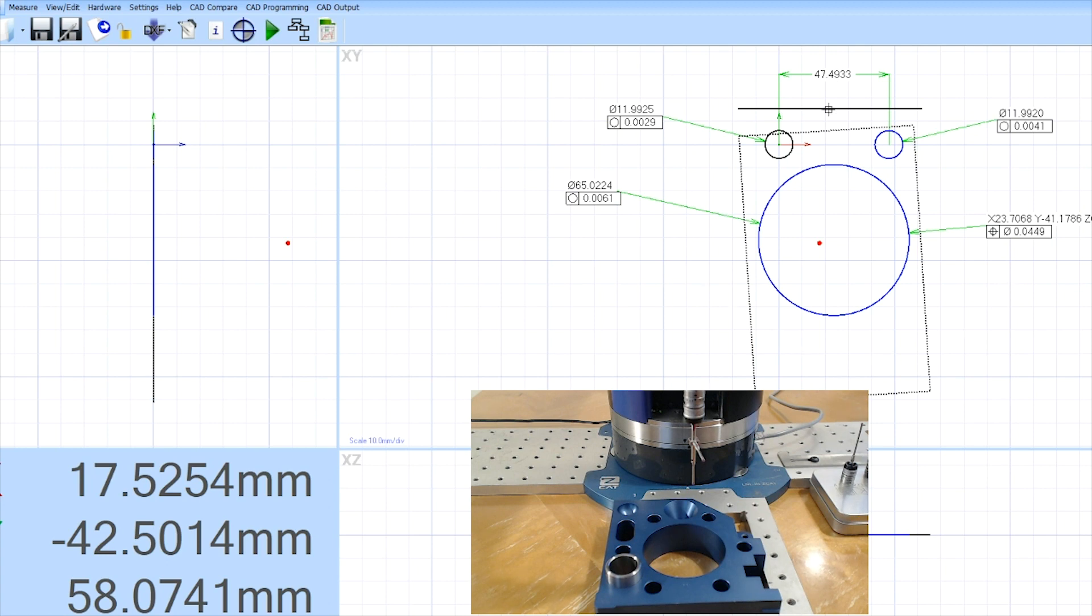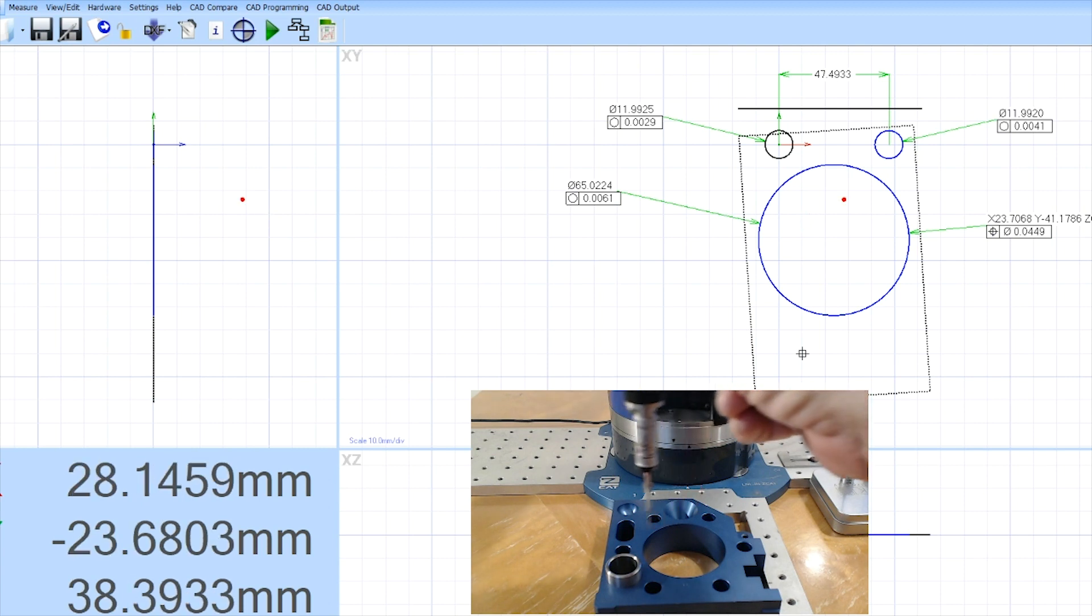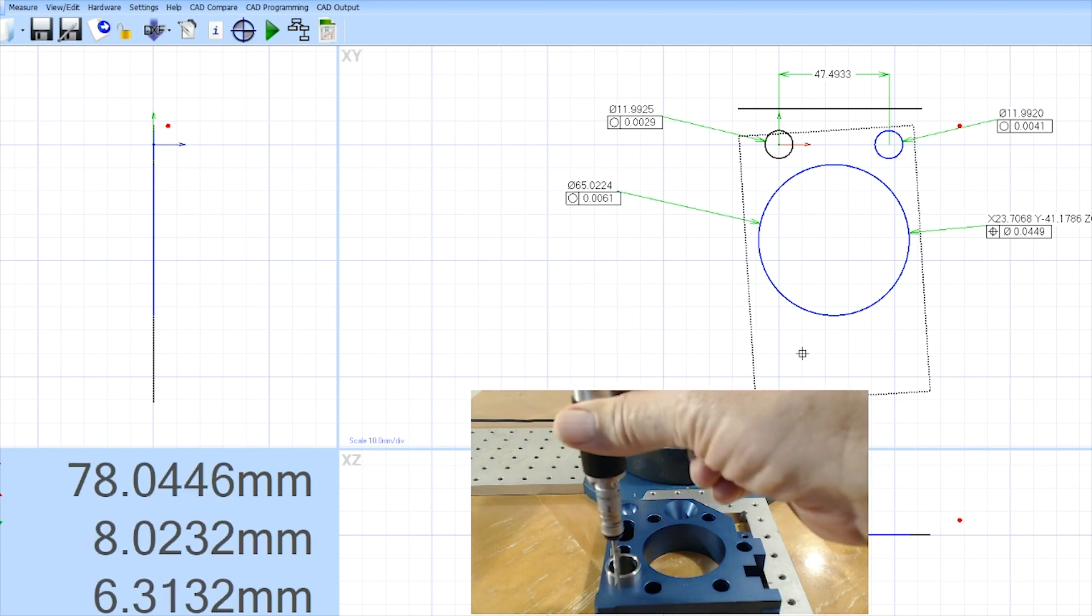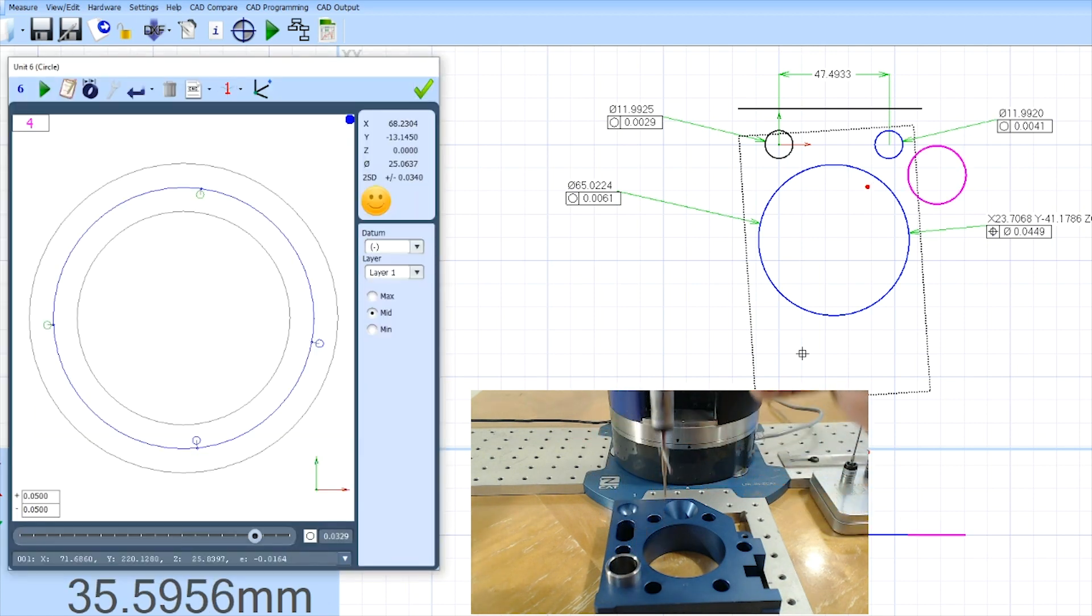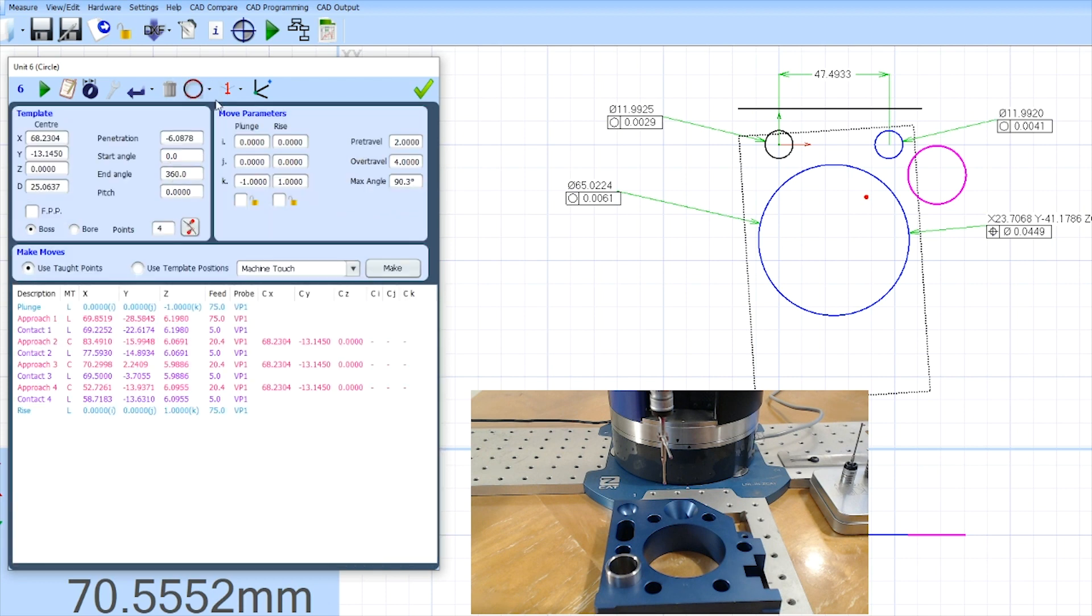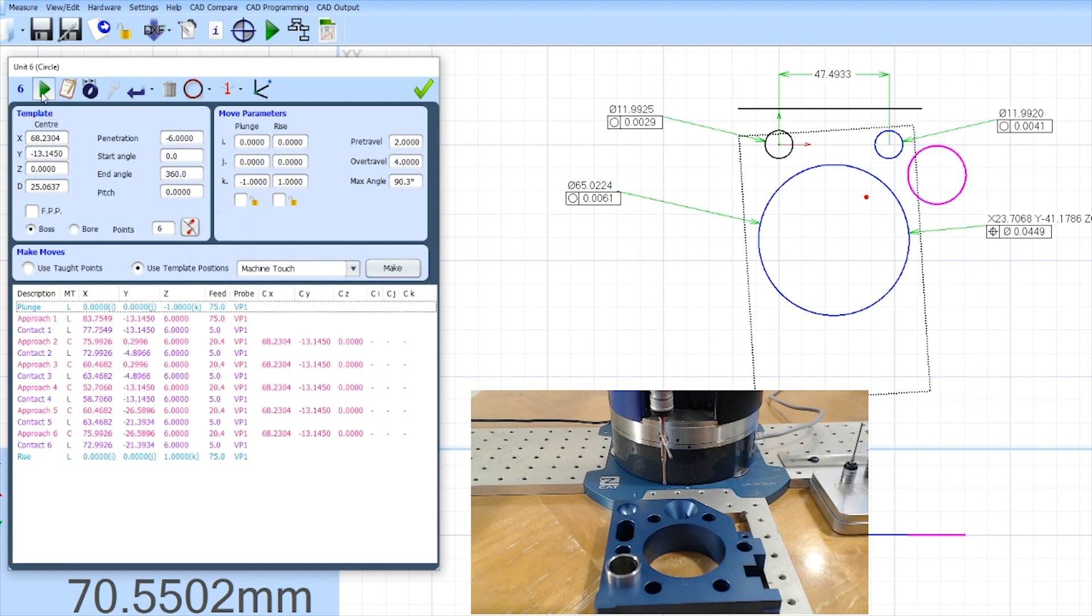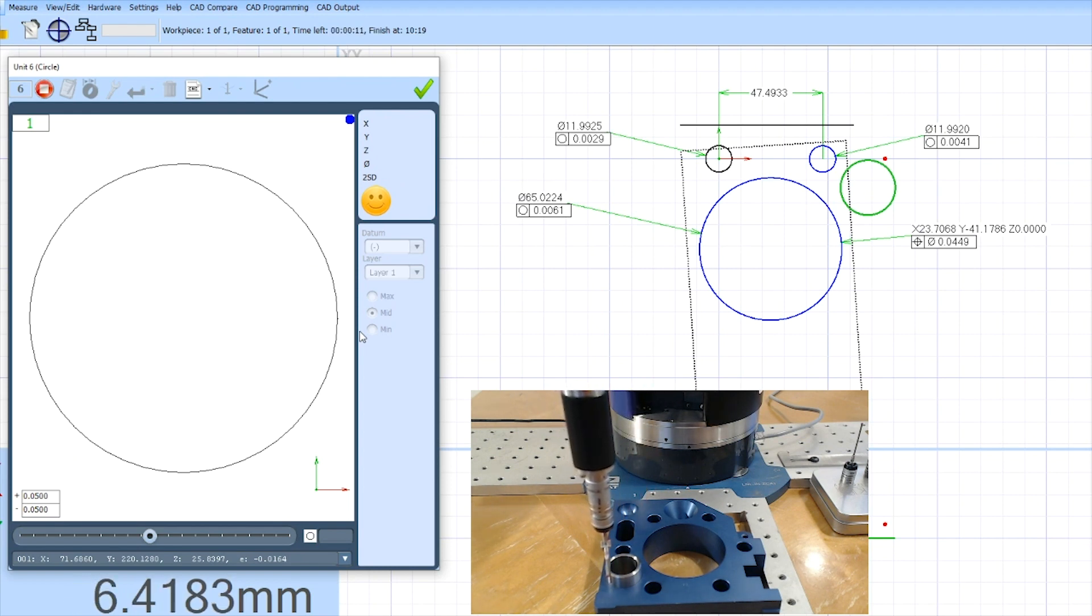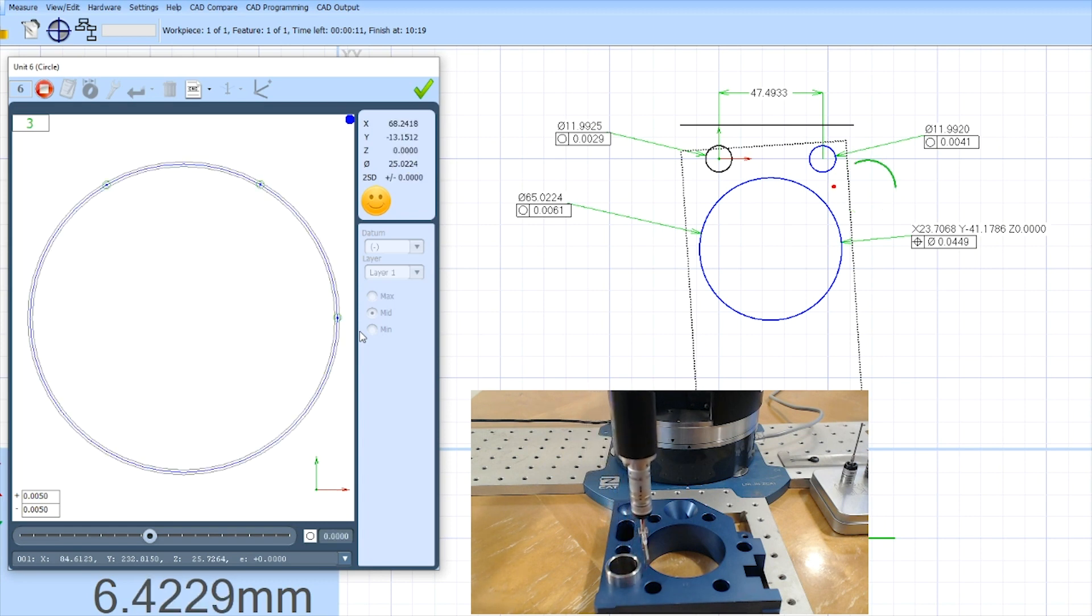So what I've done so far is a few features by hand and if I wanted to continue measuring this part with my probe I can continue with the teach and repeat. I can measure around this outside diameter. You'll see it predicted that was a diameter. I can go into my CNC portion of this page and tell it I want to take six points and I want all points to be exactly six millimeters above the plane. I can hit make and now the ZCAT will measure that outside diameter with six points equally distanced around it exactly six millimeters above my reference plane.